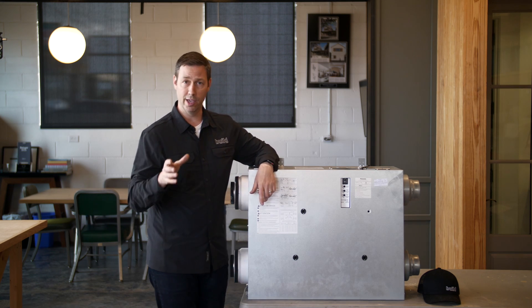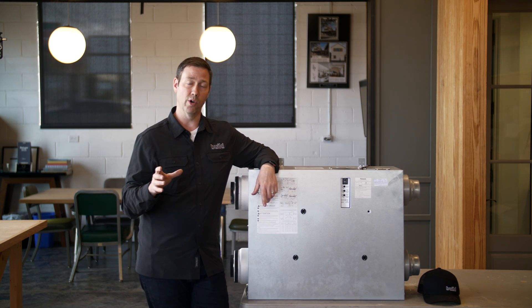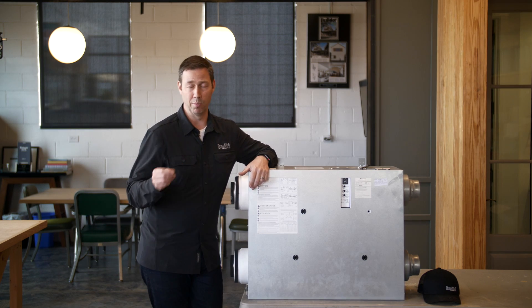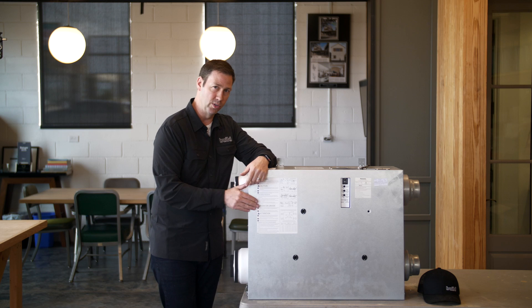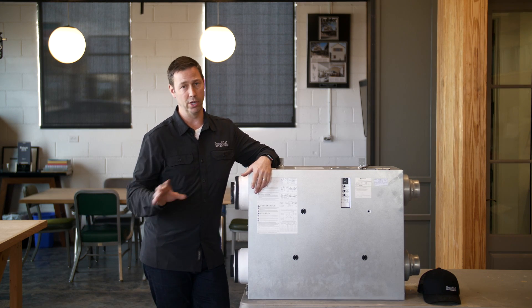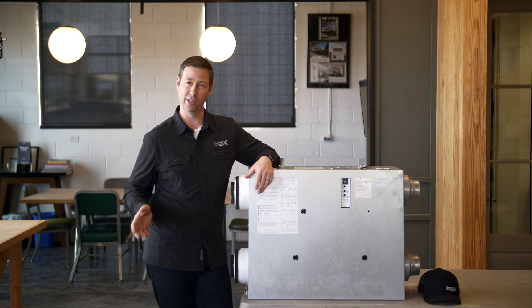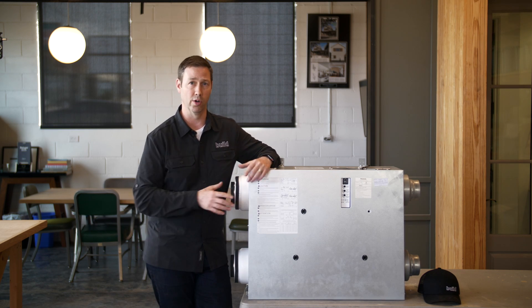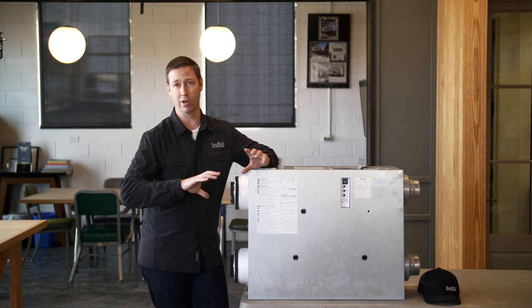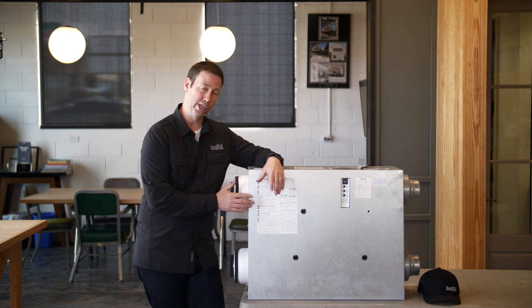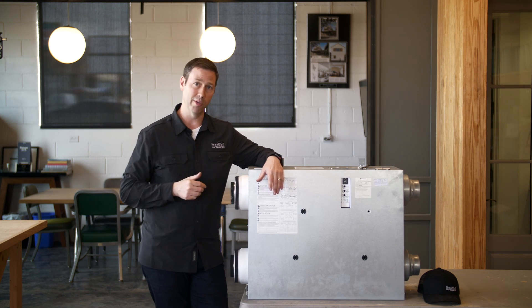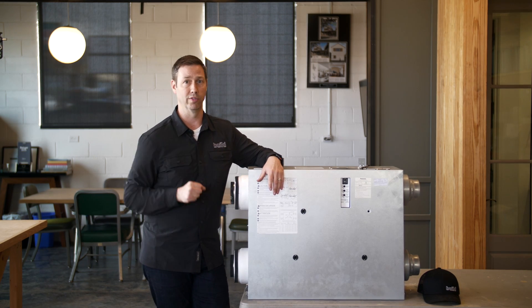If you're in the north, again, you want an HRV because we want to reduce that penalty from that cold air coming in. The last myth that I want to bust is that an ERV, if it's used in a cold climate, is going to freeze up. Now the manufacturers have solved that years ago. So this is no longer the case, maybe 10, 15, 20 years ago an ERV might, but that's no longer the case. So if you're deciding between the two and you're in a mixed climate, an ERV is a better choice because it also acts as an HRV. If you're in Minnesota, you're probably not going to need the ERV. An HRV is fine.